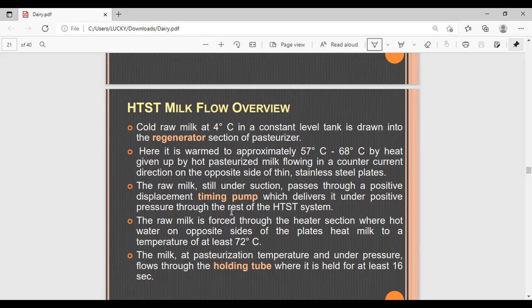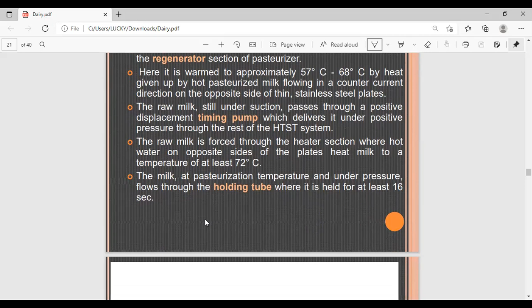The raw milk, still under suction, passes through a positive displacement timing pump, which delivers it under positive pressure through the rest of the HTST system. The raw milk is forced through the heater section, where hot water on opposite sides of the plates heats the milk to a temperature of at least 72 degrees centigrade. The milk at pasteurization temperature and under pressure flows through the holding tube, where it is held for at least 16 seconds.